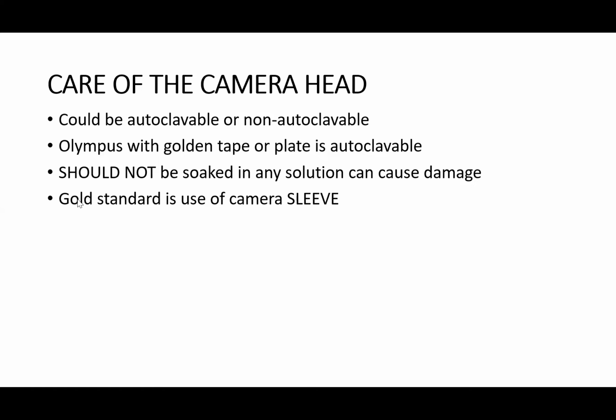We've already discussed all the parts of a laparoscopic instrument. You can refer to the previous lectures we did. Now, some of these camera heads are autoclavable and some are non-autoclavable. And if they are autoclavable, it will be indicated. Now, newer devices are autoclavable. Okay, you'll see some newer devices that even have lenses, but they are autoclavable and it will be indicated maybe by having a gold strip or tape on the camera head, like the Olympus product with gold tape or plates. Now you have to be very careful not to autoclave a non-autoclavable camera, because you are going to destroy the instrument.